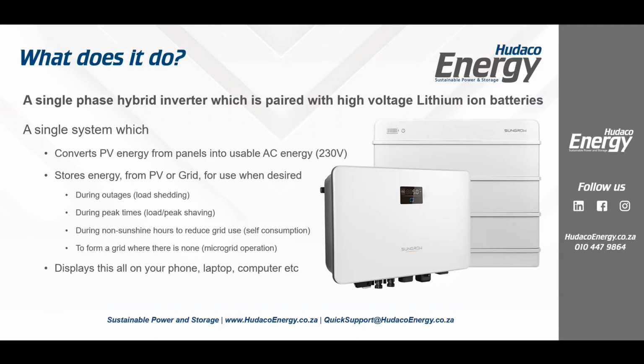What does it do? Okay, so this is not a UPS. It's not a backup system. It's not a solar system. It's an energy management system. On the PV side, it converts energy from the panels into usable energy in the home at 230 volts, being single phase. It also stores energy either from PV or from the grid when desired to do the following 4 functions. The first one is during outages in case there's load shedding, right, or grid failure for whatever reason.